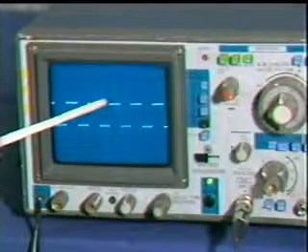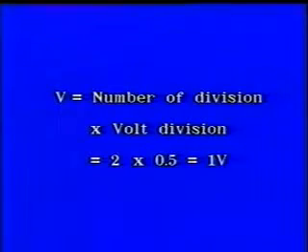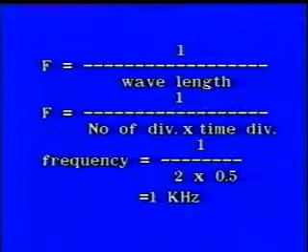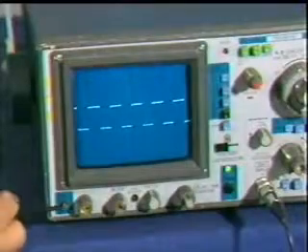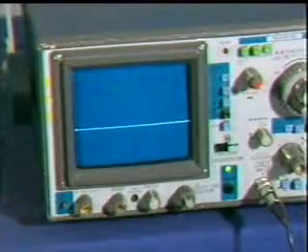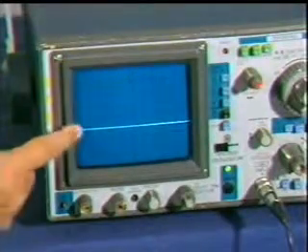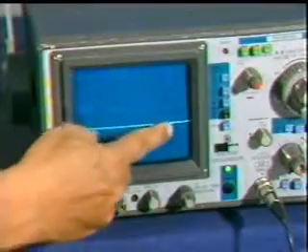To verify the one-volt peak-to-peak signal amplitude, put the measured values in the formula. The inverse of wavelength is frequency; put the measured values of the wavelength to verify the one-kilohertz signal. Then remove the probe from the calibration terminal and observe the horizontal beam.